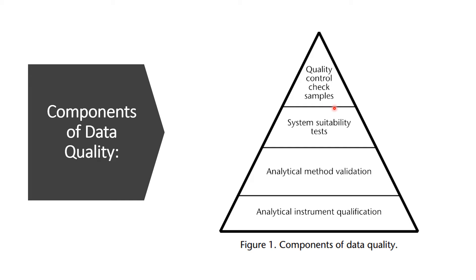Next is quality control check samples. A reference standard or calibration standard is used to calculate the result of unknown samples. QC check samples are analyzed along with unknown samples as part of routine analysis to ensure that the analytical process is under control and producing accurate results. Basically, the system suitability test and quality control check samples ensure the quality of analytical results immediately before or during sample analysis. So first, when you procure any instrument, that instrument should be qualified; then analytical method validation needs to be performed on that qualified equipment, and then you perform the system suitability test and quality control check samples so that the generated data has appropriate and acceptable quality.